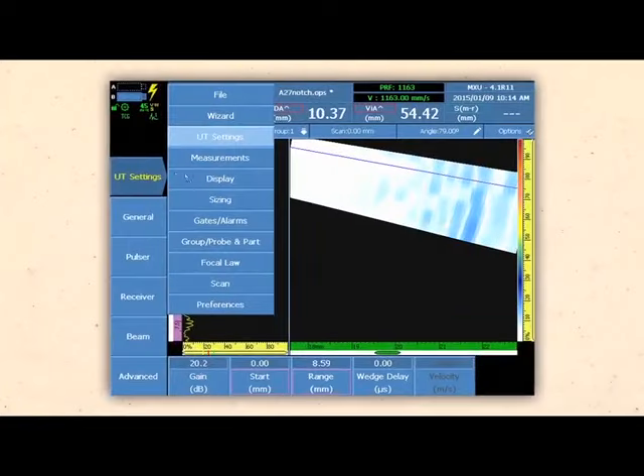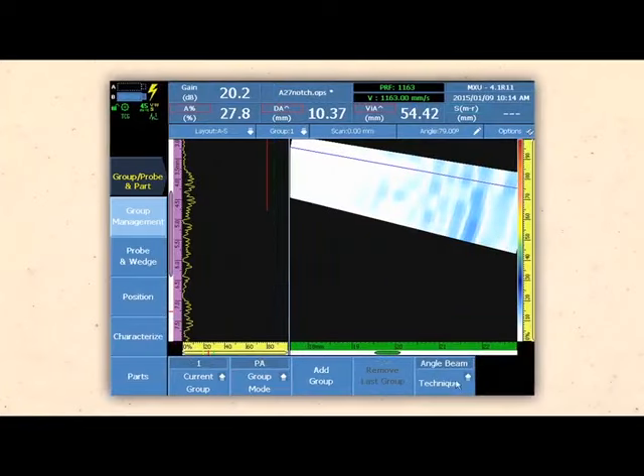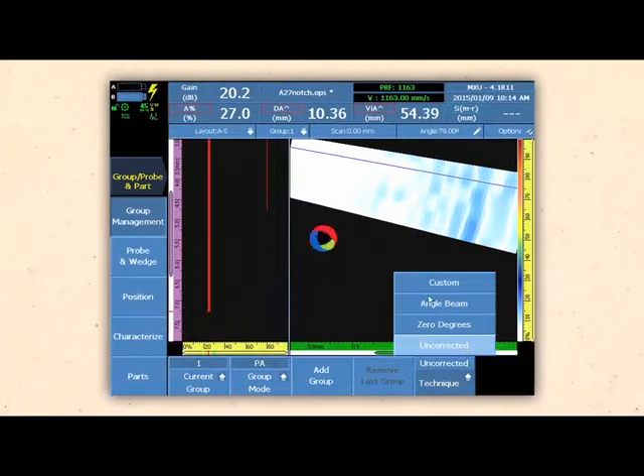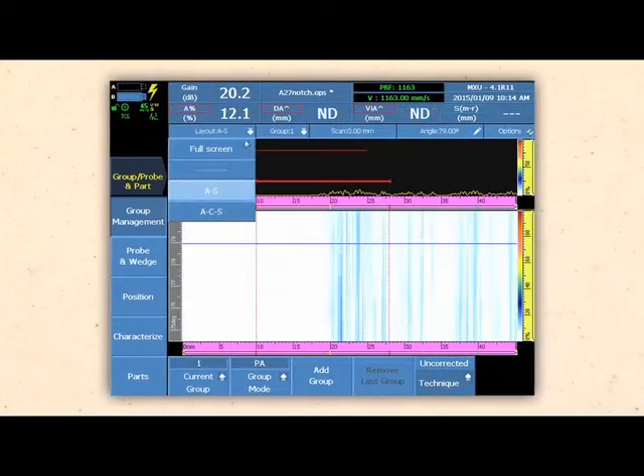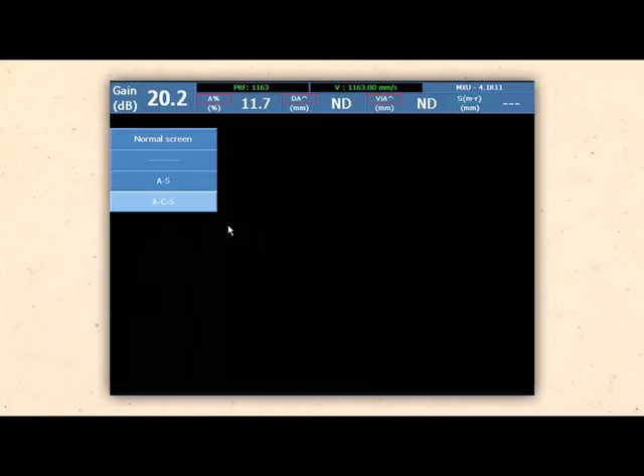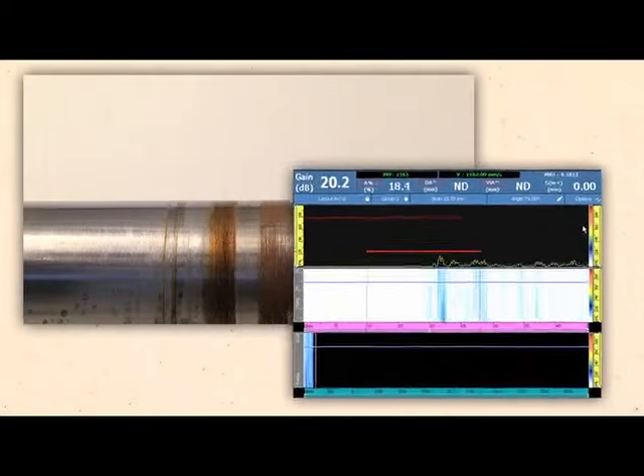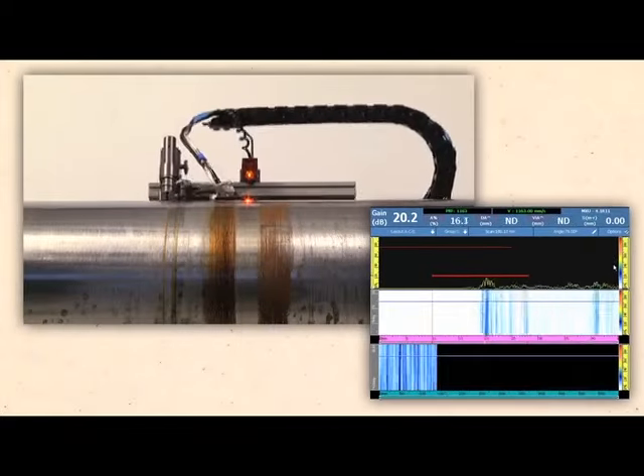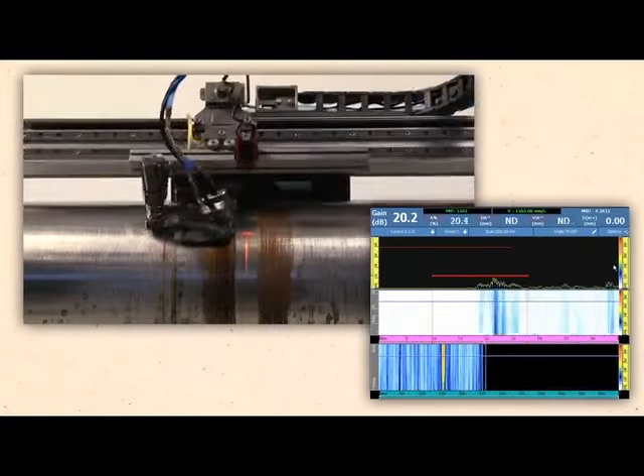For high angle surface testing, the OmniScan display is configured for an uncorrected S-scan to optimize the display size, and the gate is positioned to represent the width of the inspection area over the weld in the C-scan for detection of surface and near-surface flaws.